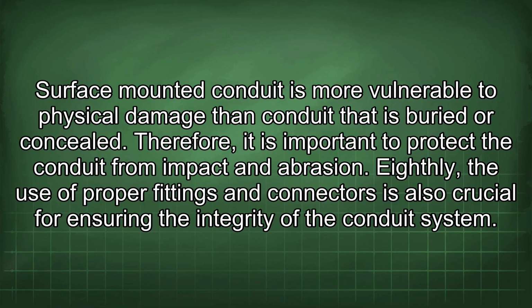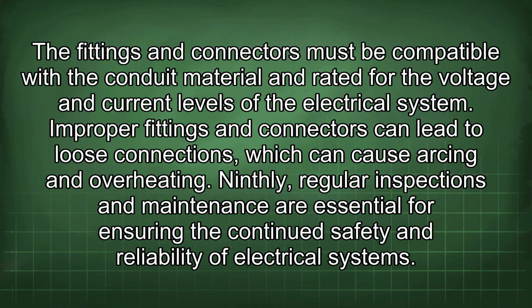Eighthly, the use of proper fittings and connectors is also crucial for ensuring the integrity of the conduit system. Fittings and connectors must be compatible with the conduit material and rated for the voltage and current levels of the electrical system. Improper fittings and connectors can lead to loose connections, which can cause arcing and overheating.